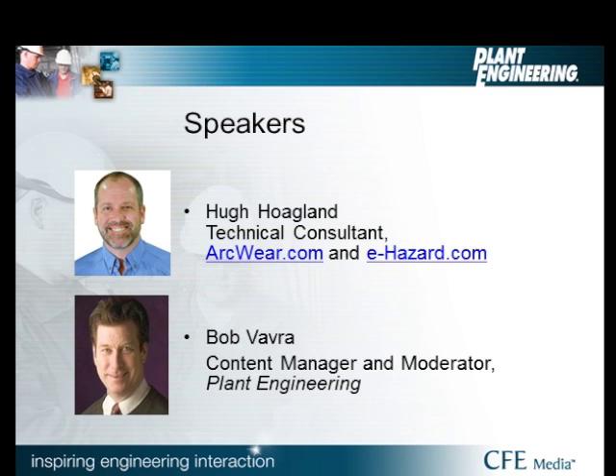Shock PPE, like voltage-rated gloves, should be replaced anytime it fails a shock test or anytime you have tackiness, several things like that. For arc flash PPE, which is probably what this reader was talking about, you want to make sure you replace it when it has a major issue. And this is really difficult.